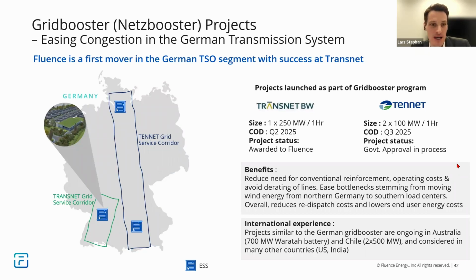So what do those assets, what do those batteries in the grid actually do? Because if we think about energy storage, we often think about, of course, charging and discharging energy. And there are certain projects like that, like the Ringo project in France, for example, where storage does exactly that to overcome grid congestion. But these batteries here are used in a different way. I always like to say, if everything goes correctly, over the 20-year lifetime of those batteries, they will not be used a single time, because they really act as a contingency reserve in the German grid.